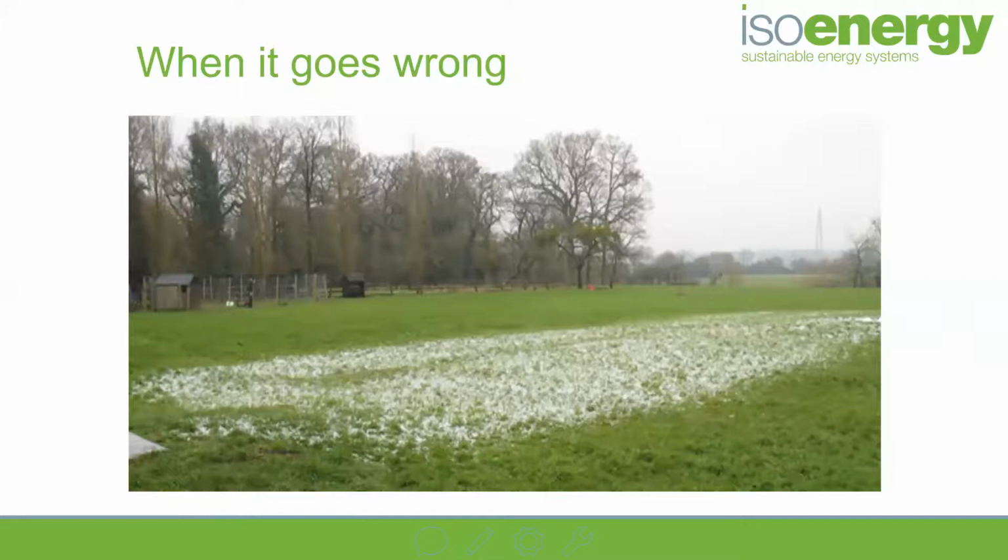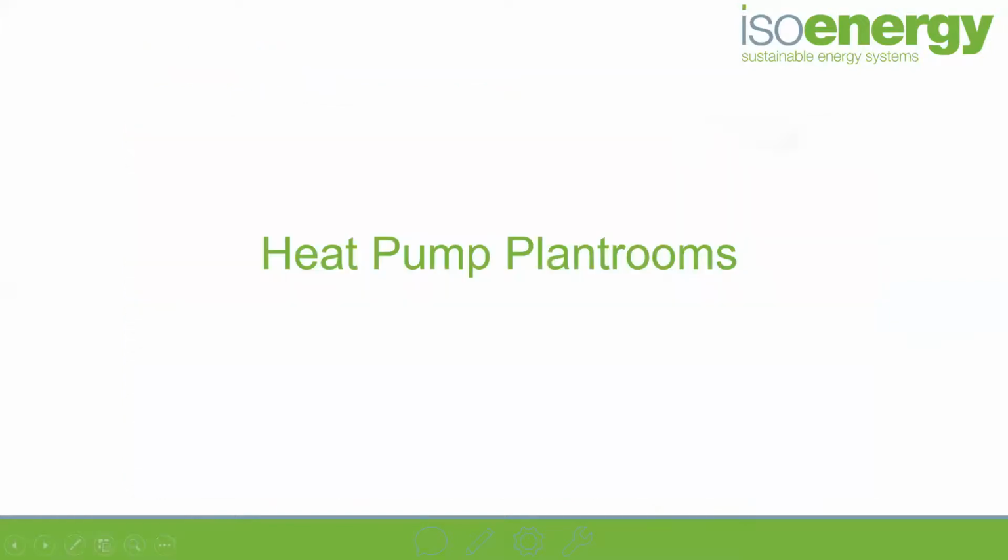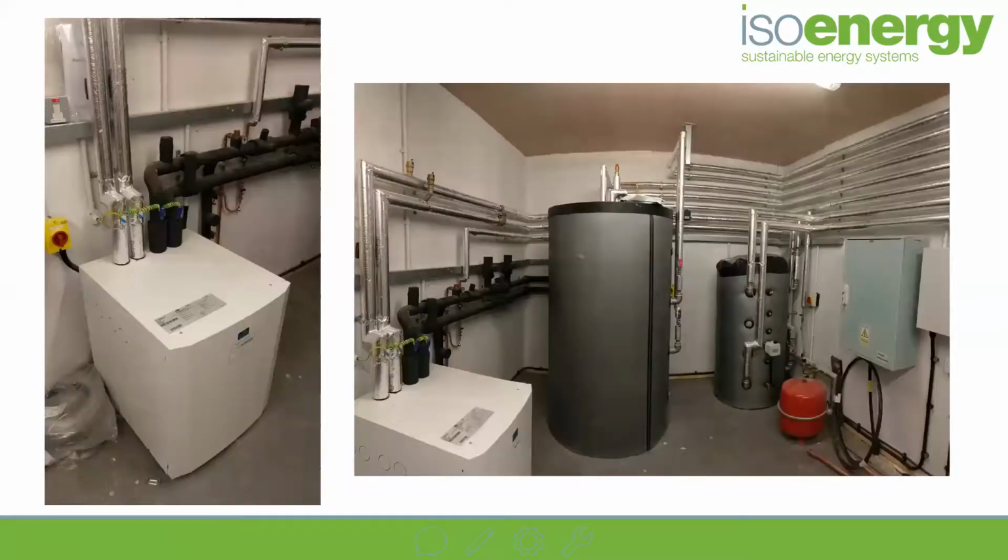So again, key design: heat pump plant rooms. This is something that's often underestimated and becomes a real trouble for us when it comes to new builds, because they've never really been factored in. They think, oh, well, we've got the utility room where the boiler is going to go. Can the heat pump go in there? No, is the short answer.